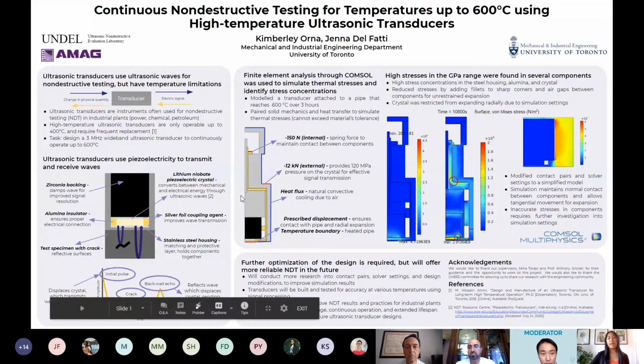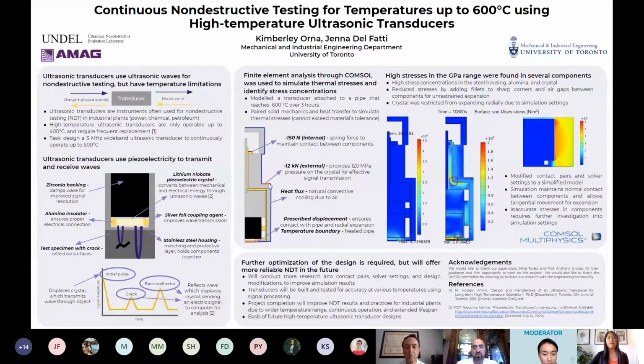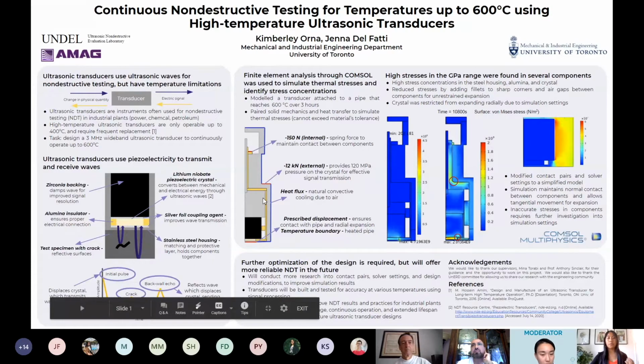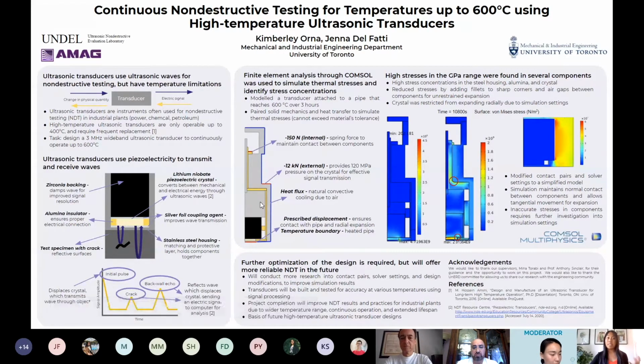So what we did was we ran an axisymmetric simulation since our transducer was symmetrical. And what we included was a boundary condition to mimic our transducer connected to a pipe that would heat up to 600 degrees Celsius over 3 hours. We thought that this was very important because the internal stresses due to thermal heat inside the transducer were going to increase, and we had to make sure that the materials didn't exceed their yield stress and break down during operation. Also, we needed to ensure a 120 megapascal load on our crystal for effective wave transmission.